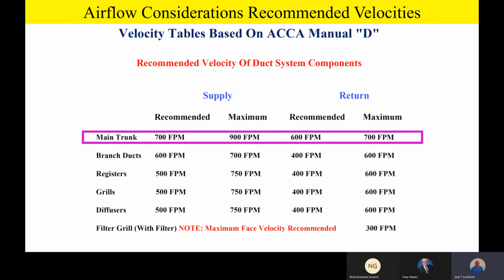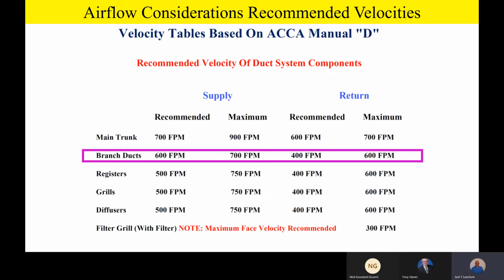Some examples would be, for instance, on a main trunk, Manual D recommends, this is right out of Manual D, a table out of Manual D, the velocity table. Our main trunk on the supply, we need to be looking for around 700, not to exceed 900. And if you've got a return trunk, 600 is recommended, not to exceed 700. On your branch runs, your takeoffs, Manual D recommends 600 feet a minute velocity, not to exceed 700, and on the return 400, not to exceed 600, and so on. So you'll see that in the Manual D velocity table, we ask that when you're designing the duct system you be sure and look at that.